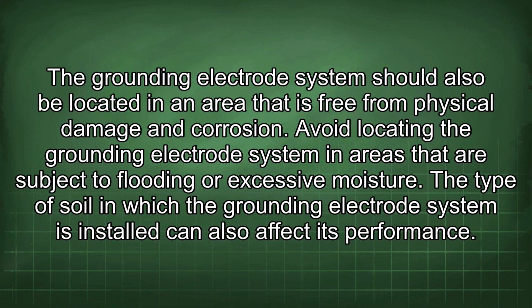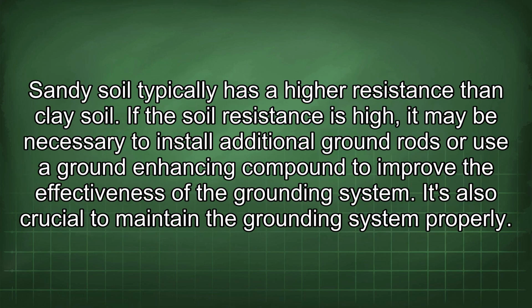The type of soil in which the grounding electrode system is installed can also affect its performance. Sandy soil typically has a higher resistance than clay soil. If the soil resistance is high, it may be necessary to install additional ground rods or use a ground-enhancing compound to improve the effectiveness of the grounding system.